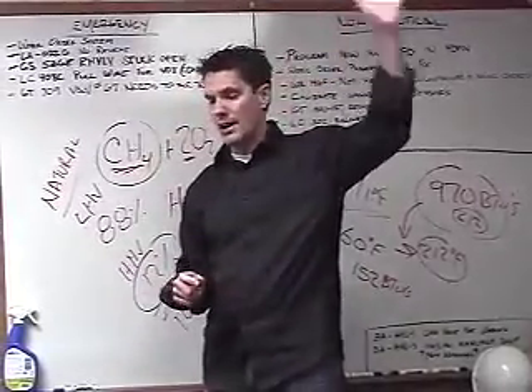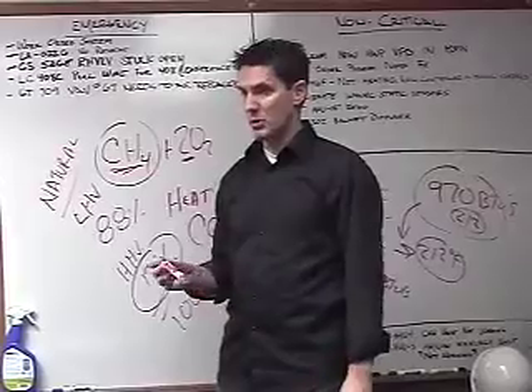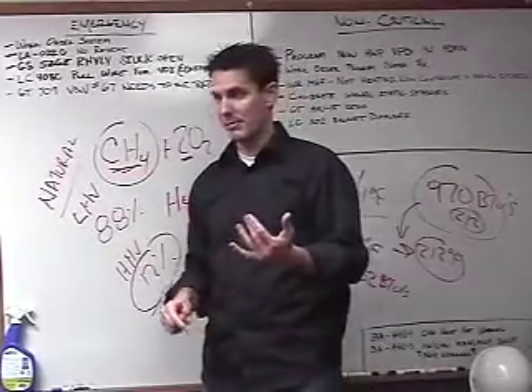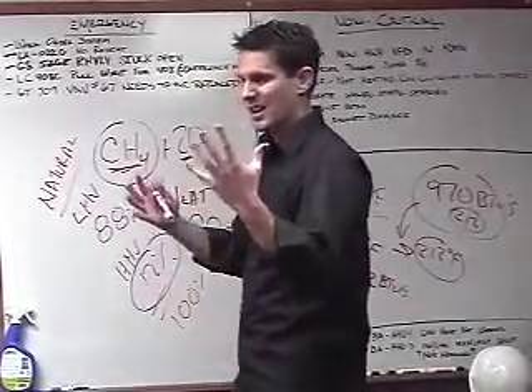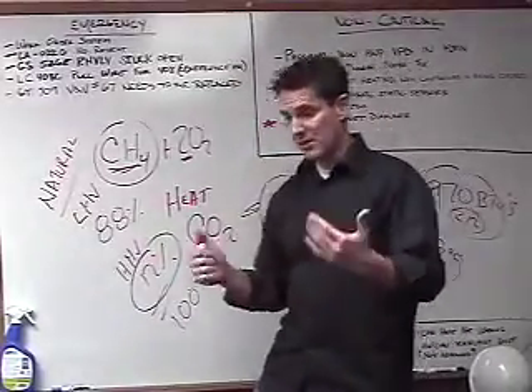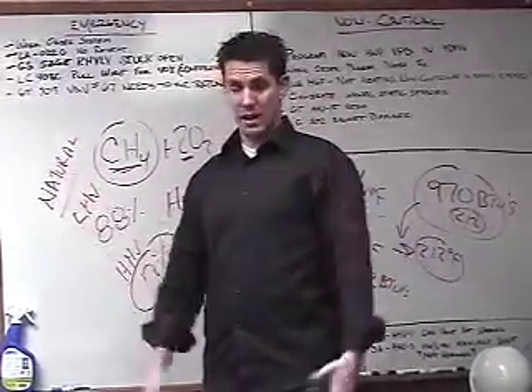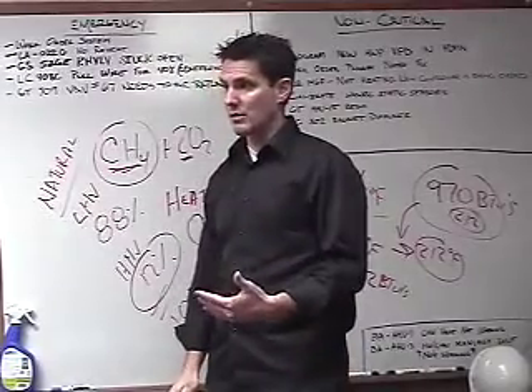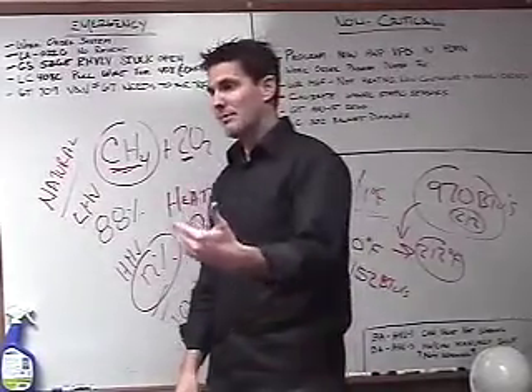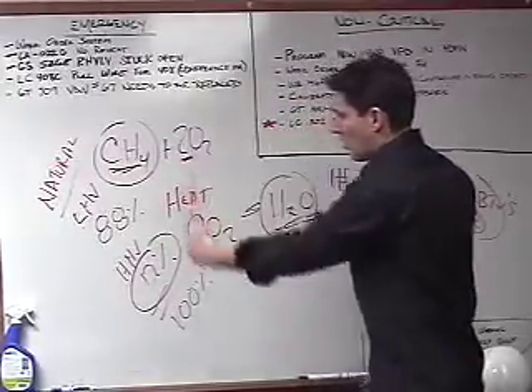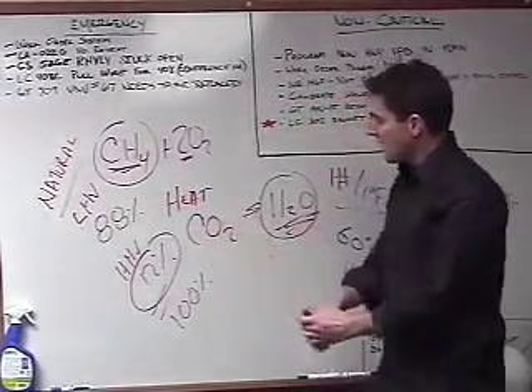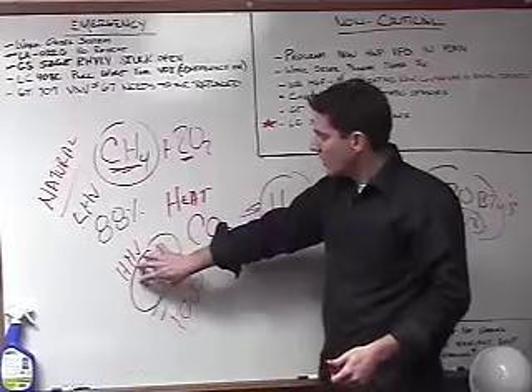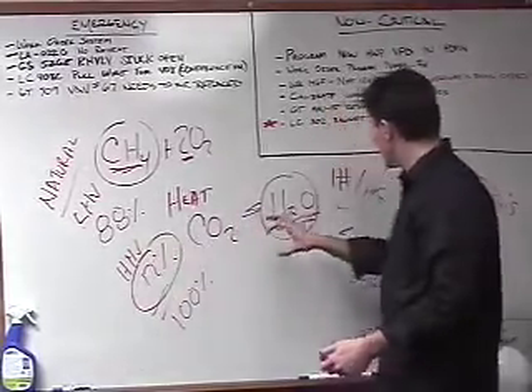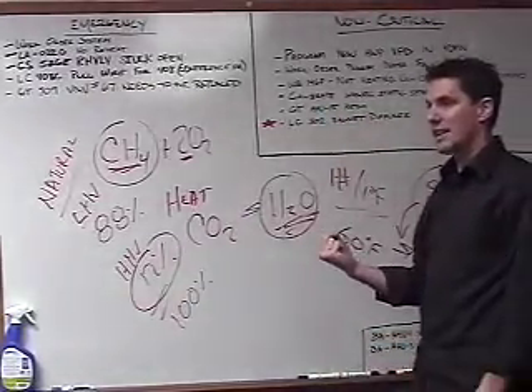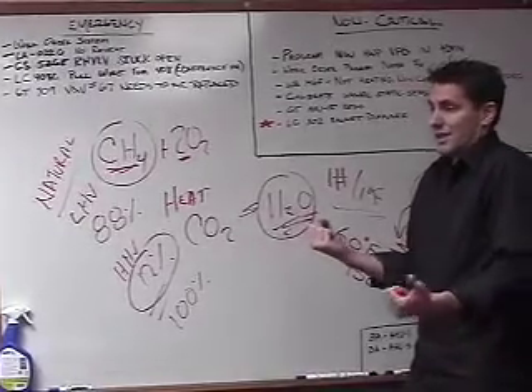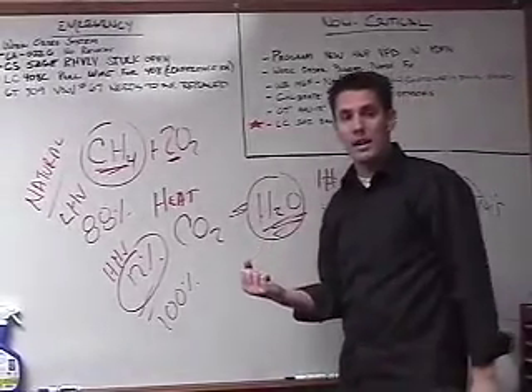Back in the day, 12 years ago, I used to sell steam boilers in the state of California. We did a lot of food processing plants, paper mills, big industrial facilities. And when I would start these big boilers up, they would condense. But it's a non-condensing boiler. Well, why are they condensing? It doesn't matter whether my boiler's designed to allow it to condense or not. If I'm capturing the energy out of this high heat value, if I'm taking this latent heat energy and condensing it out of my steam, I'll condense. It doesn't matter what kind of material the boiler's made out of.